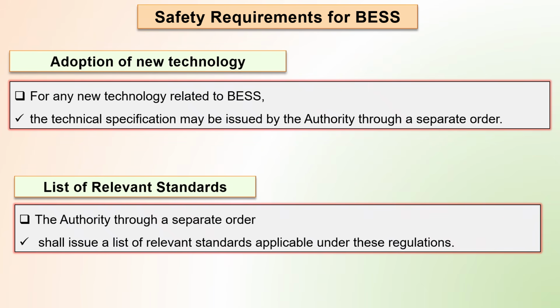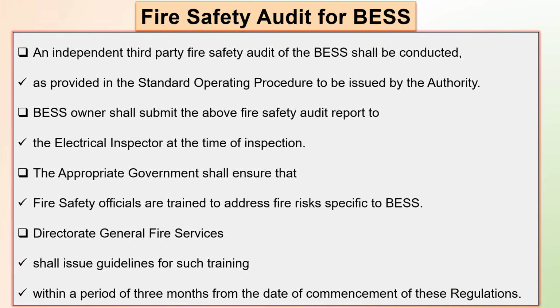Then for any new technology related to BESS, the technical specification may be issued by the Central Electricity Authority through a separate order. Then the list of relevant standards shall be issued by the Central Electricity Authority through a separate order. Then there is also a provision of an independent third-party fire safety audit of BESS as provided in the standard operating procedure to be issued by the authority. The BESS owner shall submit the above fire safety audit report to the electrical inspector at the time of inspection. The appropriate government shall ensure that fire safety officials are trained to address fire risk specific to BESS. Directorate General of Fire Services shall issue guidelines for such training within a period of 3 months from the date of commencement of these regulations.